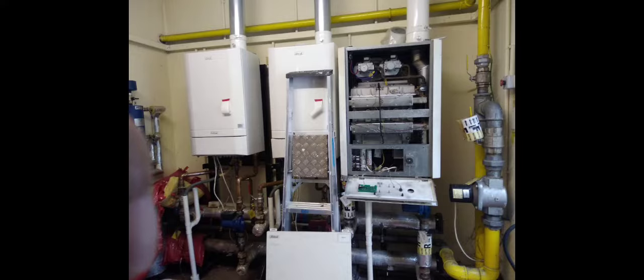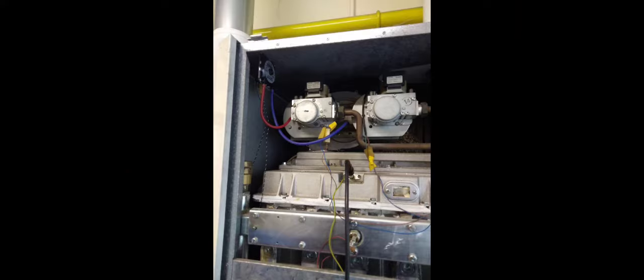We have three boilers here, two Ideals and then I think an older Ideal. I recall going to this site several times. I think this boiler on the right gave me a nightmare. I recall changing the air pressure switch, cleaning up the hoses, cutting them down and cleaning them out. I recall taking out the burner and washing it down, and it was quite a state. And this boiler still wanted to come up with a fault, so I never got to the bottom of this one.